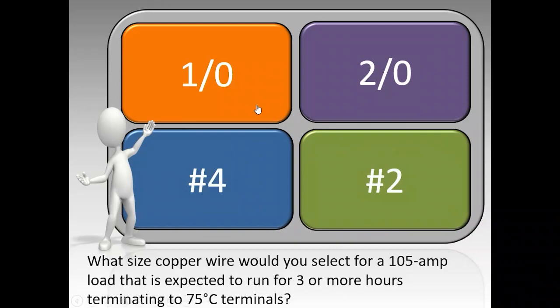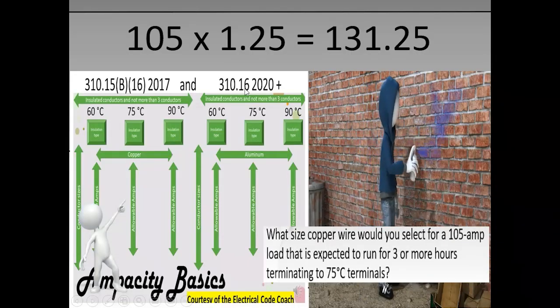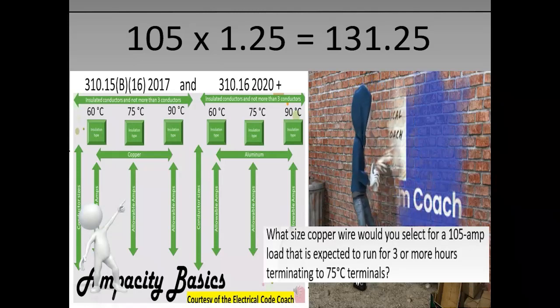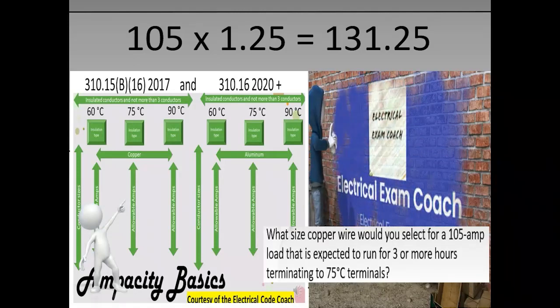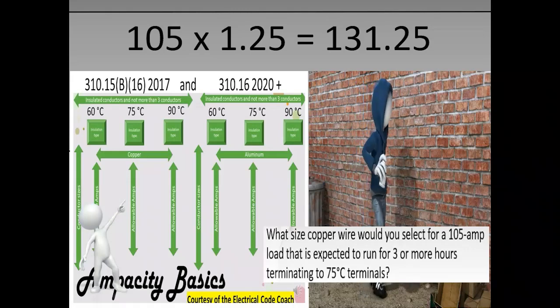The correct answer is 1/0. For this one, we're going to take our starting ampacity and multiply it by 125%. That's going to give us a new known load of 131.25.